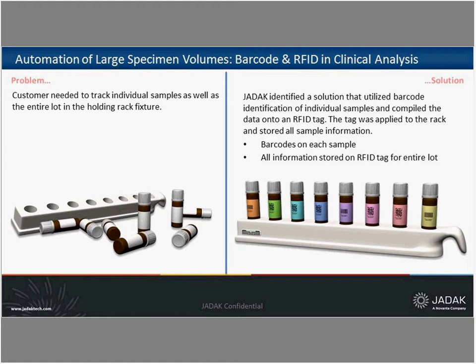Now, barcode and RFID in a clinical analysis device. As I mentioned, this uses both barcode and RFID. This is for a large clinical chemistry device. Racks with multiple samples were inserted into the device. All of the sample vials were barcoded with a unique identifier that linked that sample to specific patients. As the racks were inserted into the device, a barcode reader would read and report the barcode and position information of the sample to the host. Once fully inserted, an RFID interrogator was able to write the ID and position data into an RFID tag that was on the rack.